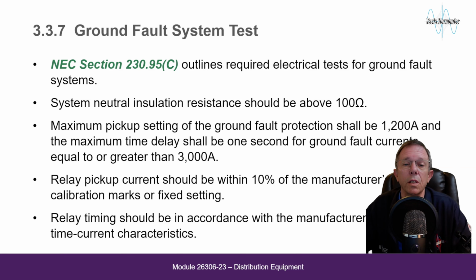System neutral insulation resistance should be above 100 ohms. Maximum pickup setting of the ground fault protection should be 1200 amps, and the maximum time delay shall be 1 second for ground fault currents equal to or greater than 3000 amps. Relay pickup current should be within 10% of the manufacturer's calibration marks or fixed setting. Relay timing should be in accordance with the manufacturer's published time current characteristics.